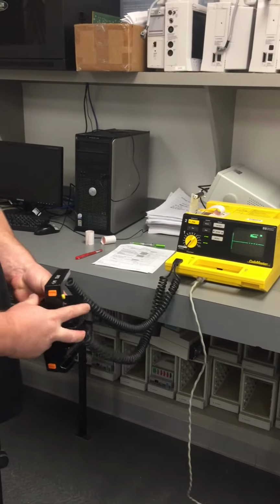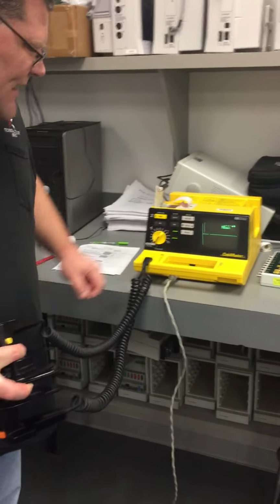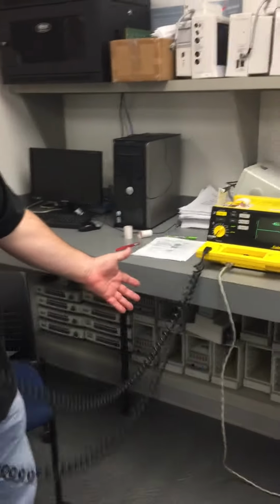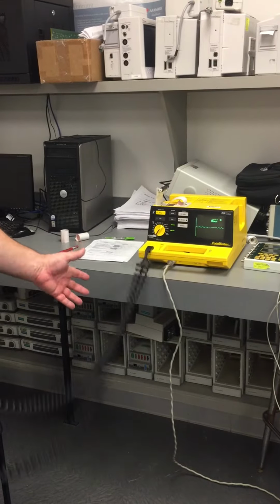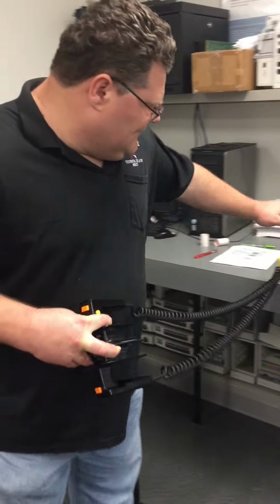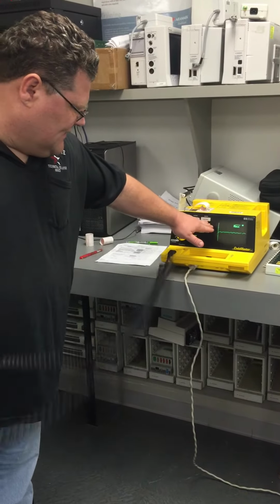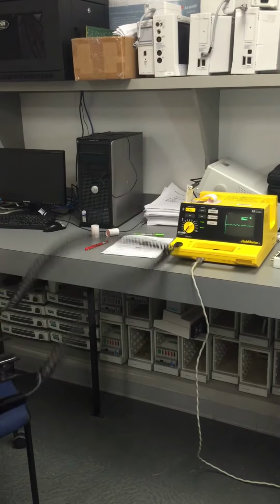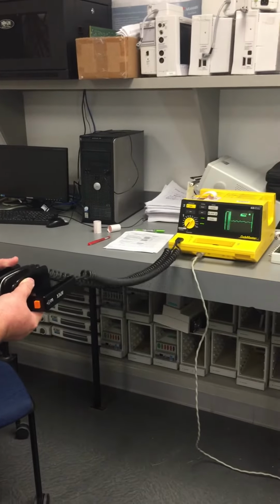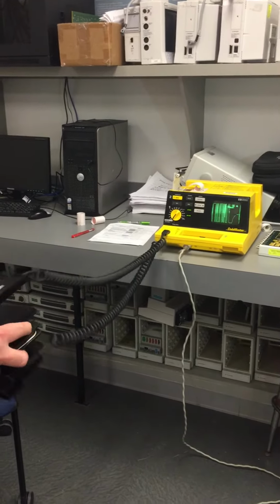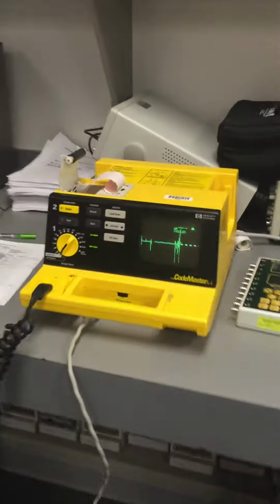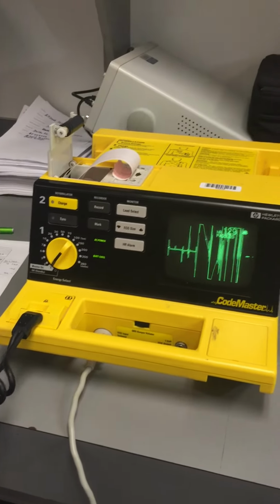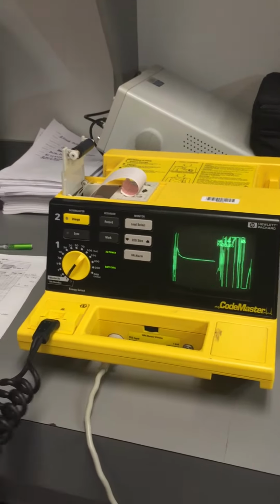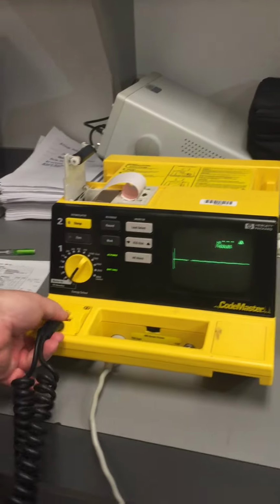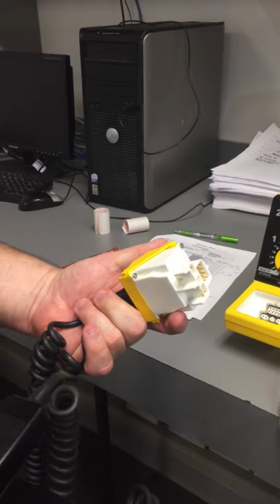Now you'll notice the ECG on the screen goes to a flat line. I'm going to stretch the pads and shake them a little bit. The reason I'm shaking them is I want to look for a nice even wave on the screen. That's actually a pass. Here's what's not a pass. If it looks sudden like this, that would be an indication of a broken cable. If you see a really sudden, stark break like that, that's an indication that the cabling, this pad right here, needs to be replaced.